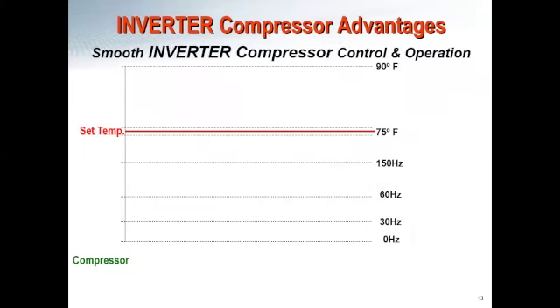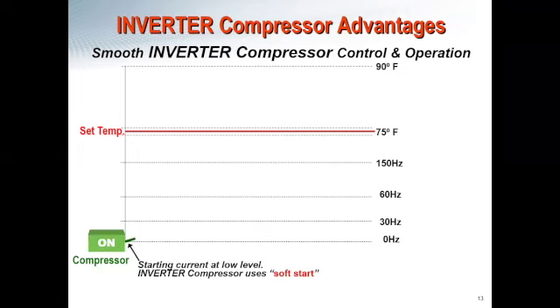So we use an inverter compressor. And one of the main differences is that with an inverter compressor, we don't have to adhere to that strict 60 hertz limit on the top end of our compressor scrolling. So when we have the call for on, we start off at a very low level, very low amp draw. And this is the same of all VRF systems. You're going to bring in a very low amp draw immediately and then turn it on to super high gear.